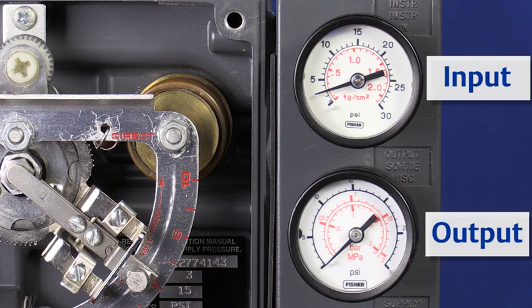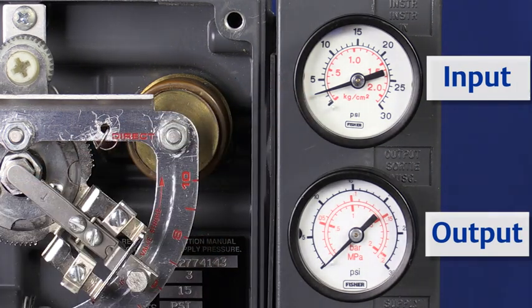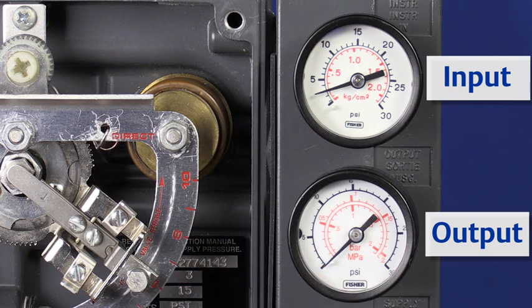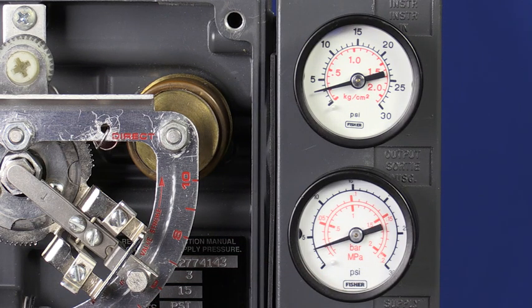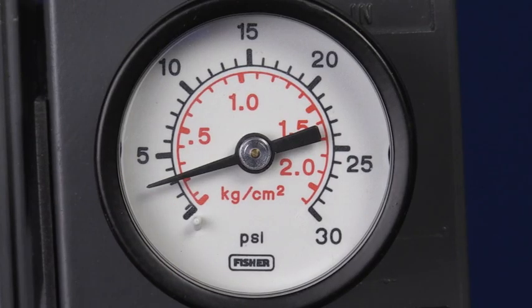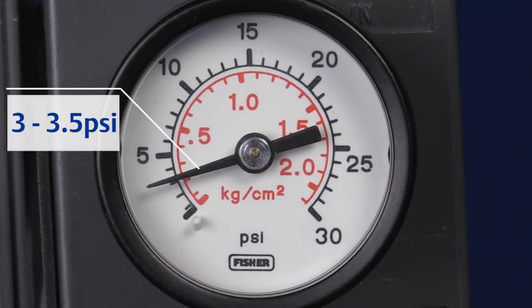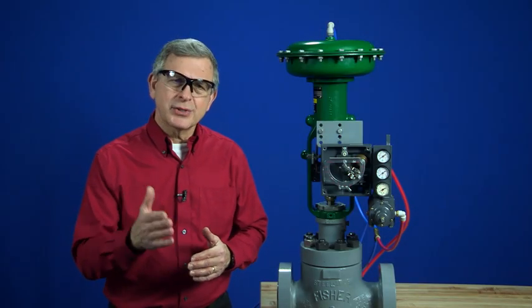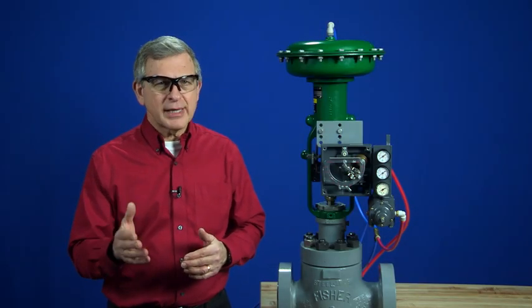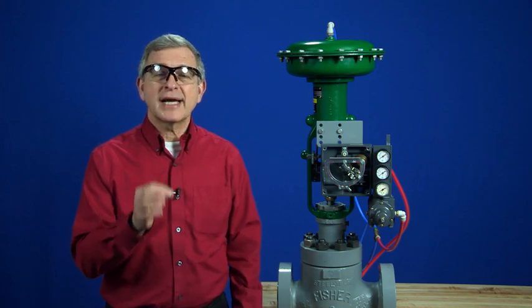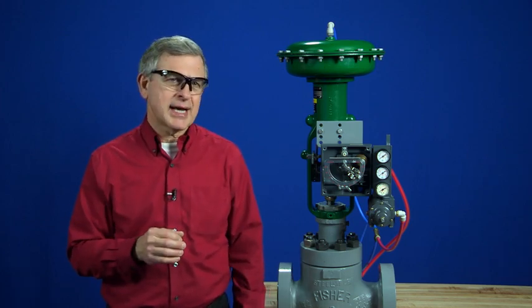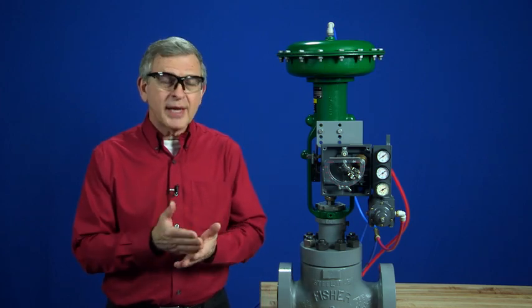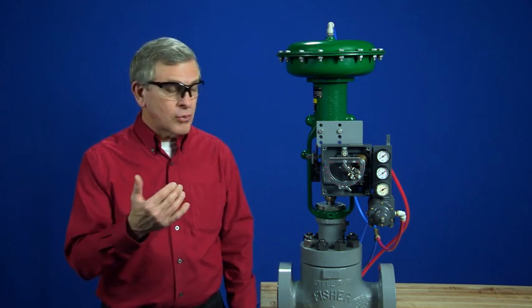Step four is to slowly increase the input pressure while watching the output pressure gauge. As soon as the output gauge needle moves, I stop the input and look at the input gauge. Ideally, it should be somewhere between three and three and a half psi. This technique makes certain that when the input is at three, the positioner output is saturated to zero psi, and the control valve is at one end of its travel, in this case, all the way open.